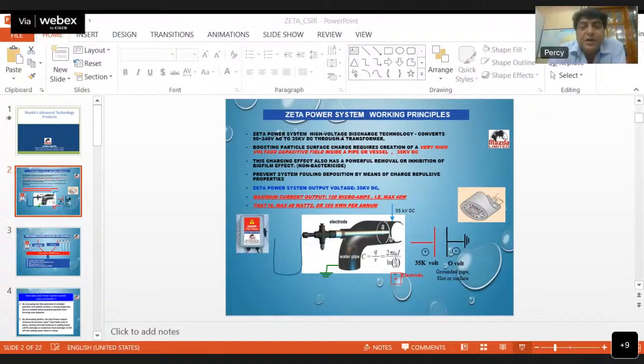This was developed by us specially to retard the scaling formed in a cooling water system. When there is scaling, there is retardation in the heat transfer of equipment like heat exchangers or reactors, whether cooling or heating. This drop in heat transfer reduces plant efficiency by 15 to 20%. It's a big issue, and to overcome it we developed this new Zeta power system. This is the product we are going to speak about today.